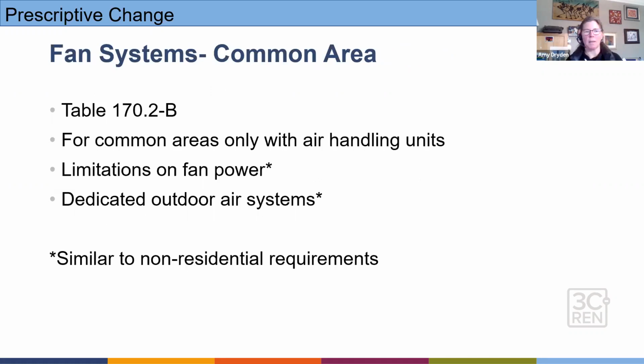Again, for common area fans, where we're looking at fans that are moving air between conditioned spaces, or tempering air, bringing it in or out, or filtering air into common area spaces, there are additional new requirements limiting that fan power. So there are fan power limitations and an energy budget. And there are specific requirements for dedicated outdoor air systems. You'll see it abbreviated as DOAS.